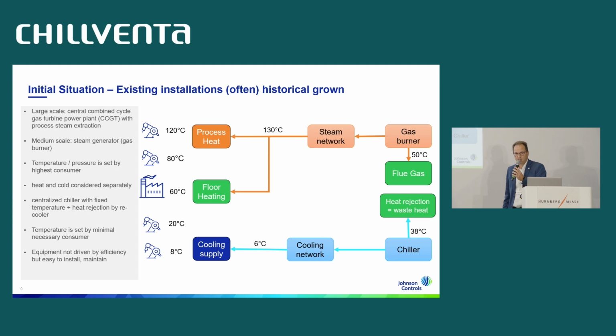What comes to my mind is that heat and cold are simply separated. This is considered separately: you have the heat provided on top, and the cooling provided below. This is a chiller, and here you have the gas burner, and beside it a massive amount of rejected heat which can be used. Typically you have a centralized chiller with a fixed temperature, which is also set by the minimal necessary consumer, although there might be a cooling demand in process equipment which is even higher. The cooling network is driven at the lowest temperature available. So you have to rethink that a little bit.